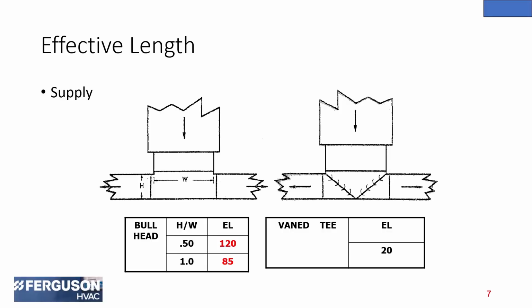Same thing applies to a downflow application with the same type of fitting. With the one with the right angles in it, you're going to have 120 equivalent length. And by putting turning vanes into that fitting, you're going to reduce the equivalent length to 20 feet, which is going to greatly reduce your external static pressure.